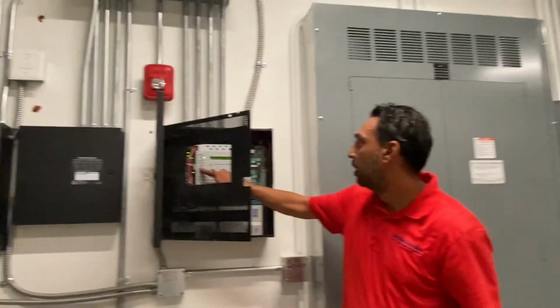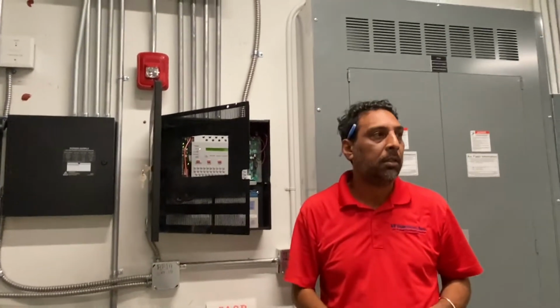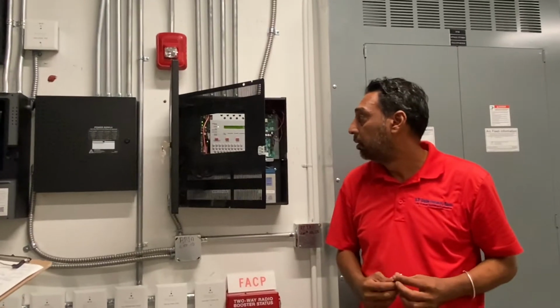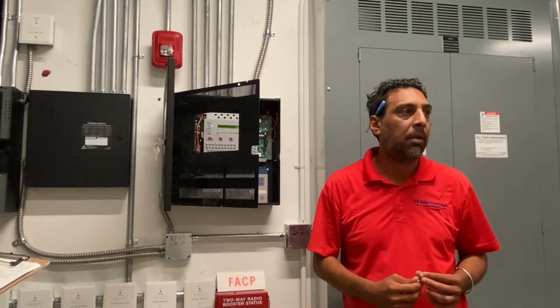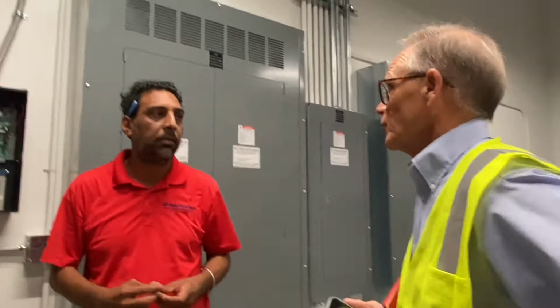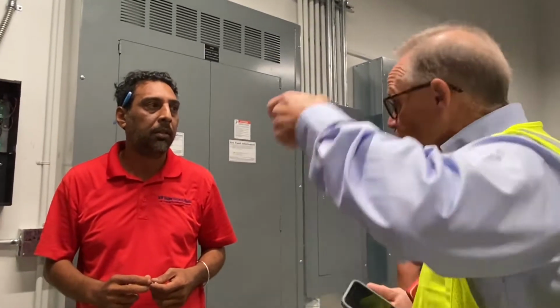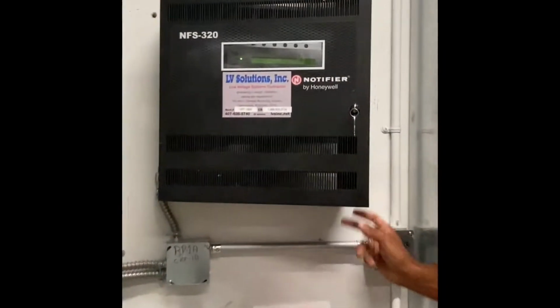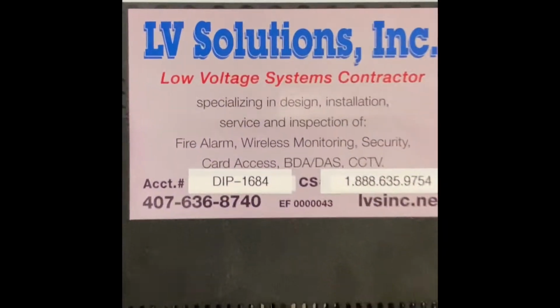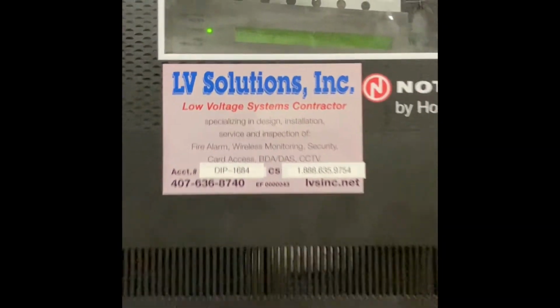Yeah, there was a group in there pressure washing the pool decks and some of the walls, and I think it may have hit it, but it just kept going off. I got called by the dispatcher multiple times. And we asked them to put that pull station, just that one, in test mode. Which they did. And it got addressed. It reports by point, so yeah, you could put that zone or that point on test. Right. But other than that, maybe I'll find out. I don't think there's a password or anything on the account. Now this is our office number on the bottom there.